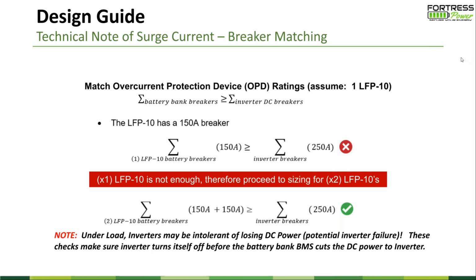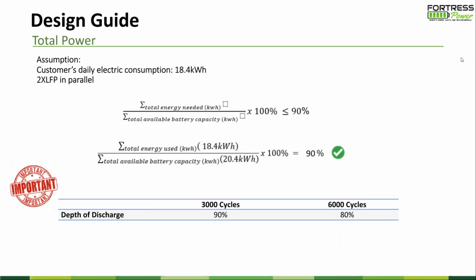Okay, let's go to the next slide. Then we can look at the total energy, how we size the capacity of the battery bank. That's another angle to look at it. So remember 4 angles. The first 2 angles are continuous power and surge power. Now we want to look at the third angle, the total energy needed. Look at the critical panel, as I showed you in the first slide, with the energy sizing tool, our Fortress Power sizing tool. Then you add up everything, and it gives you the total energy and the total power you need continuously. With the hours, that becomes the total energy you need for a day.